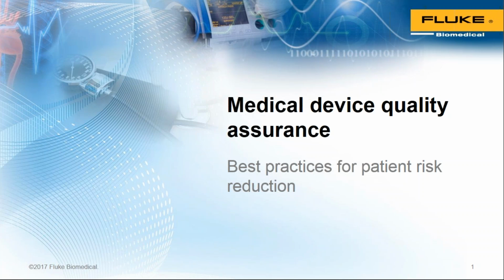Yes. The only products, devices that you cannot do that test upon are the Class 2 medical device. When I'm speaking of Class 2, I'm talking about the kind of medical device that is double insulated. This is for electrical safety purposes, not US FDA classification. So the Class 2 device has no ground, no protective earth. There's no third pin, ground pin on the power cord, because it is intrinsically safe due to the double insulation. So you won't be able to do an earth bond test on that device.